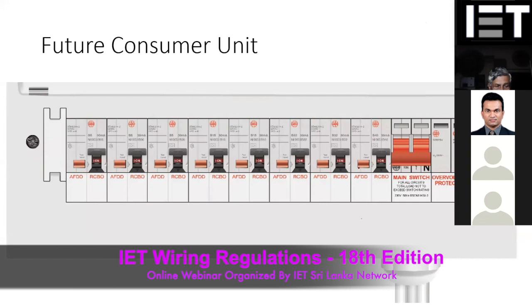Now you can see when you look at the consumer unit or the distribution board of the future, the new regulation has introduced surge protection as a compulsory requirement, and arc fault detection as a compulsory requirement for certain installations. Because of that, the design will be completely different. Earlier we were discussing only the RCD and the MCB or MCCB, but now there are new requirements beyond those: you have arc fault detection as well as SPD.